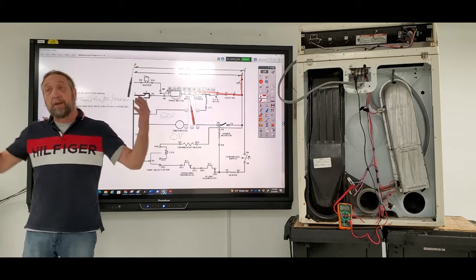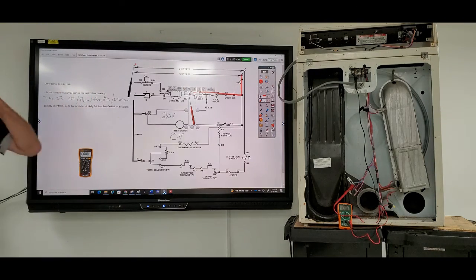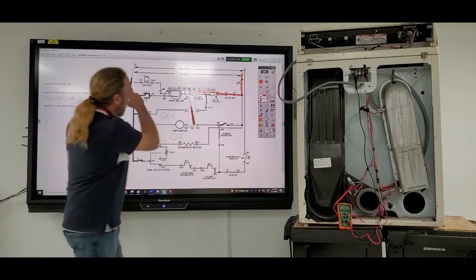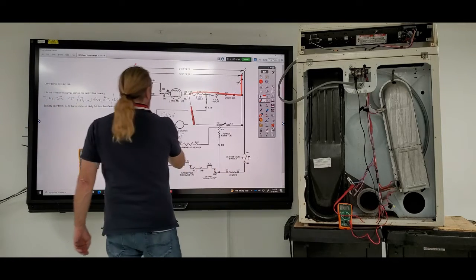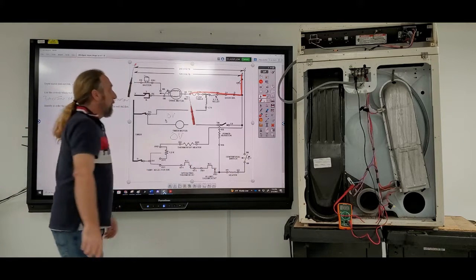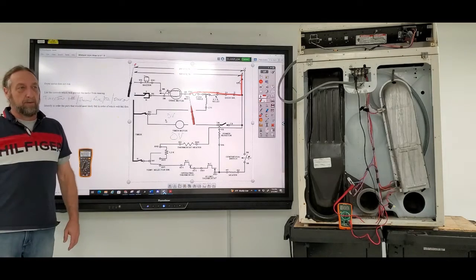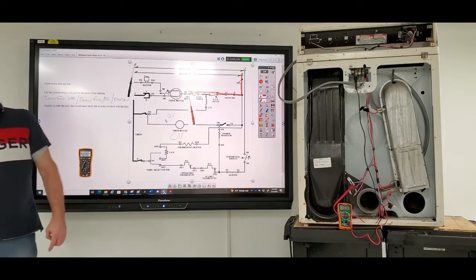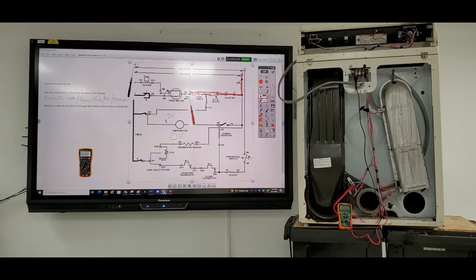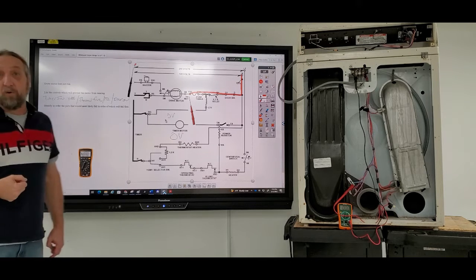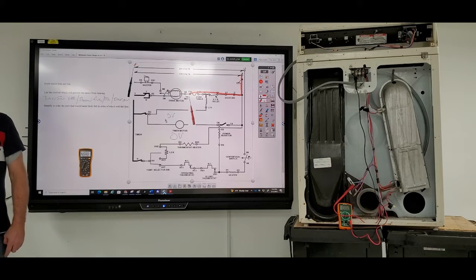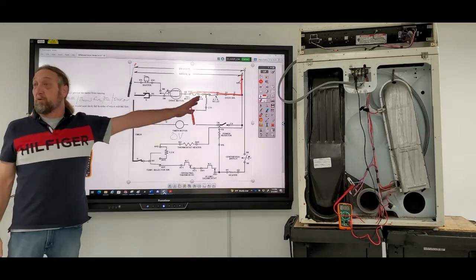If you don't have voltage, find out where the voltage is. What if my meter said 0 volts when I moved the black meter lead there? You have to hold down the push to start. Okay, well, we have to press the start button in order to complete that circuit. Let's assume I did that, and my meter still said 0 volts. Then you may have a break in the neutral. My problem's on the neutral side.